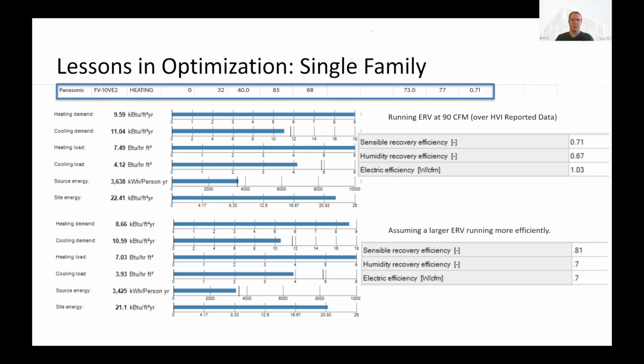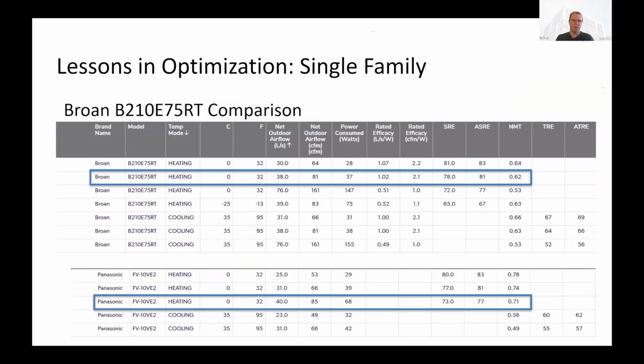If we were assuming a larger ERV, something that could run even at 81%, which is good, but not super spectacular, look at the difference in the heating demand in this case. We go from 9.59 kBTUs down to 8.66. So again, a full kBTU of energy use in this project for the heating demand just by increasing that sensible recovery efficiency, simply by maybe in this case, switching from a Panasonic or 100 CFM unit to something that's more like 200.